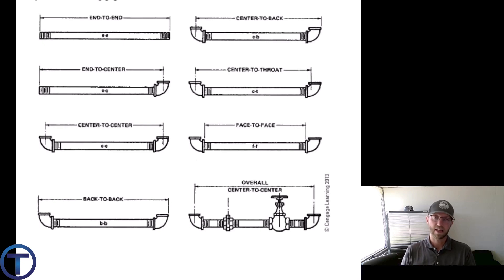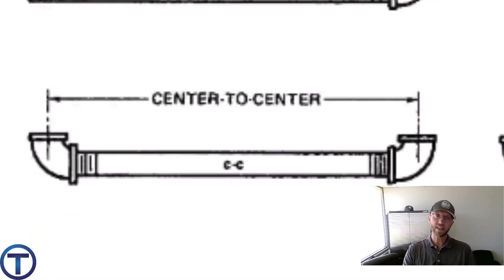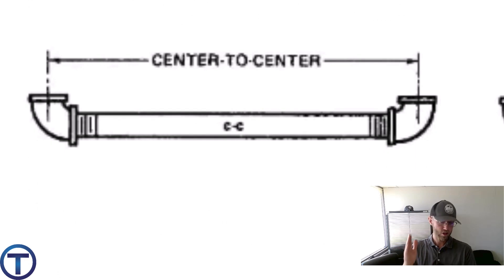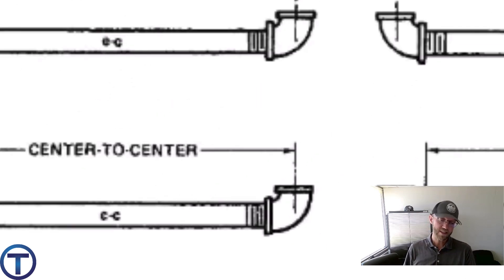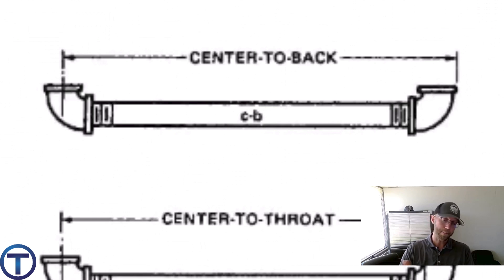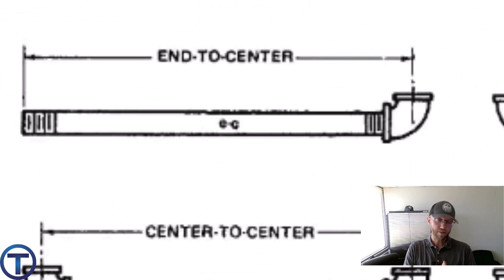Our goal is to get end-to-end measurements — that's the pipe we cut. Most of the time we deal with center-to-center, then deduct our fitting allowances. But there are alternatives that can be easier when measuring with a tape in the field. For example, center-to-back means pulling from the back side of one fitting to the center of the next — useful if you already have a pipe end out there to pull from.